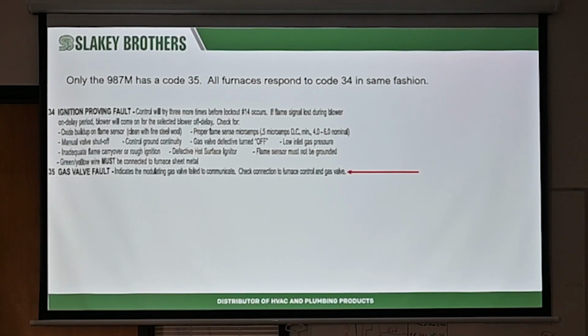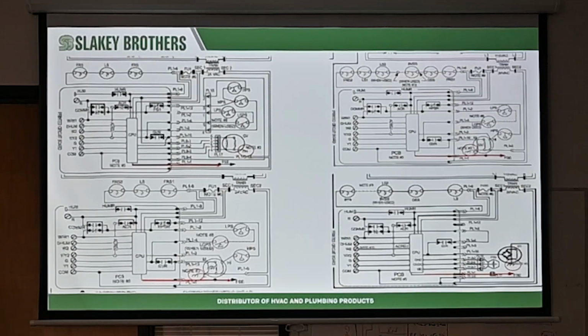Okay? So on 34, again, that's why the very, very first thing it says is oxide built up on the flame sensor. They talk about steel wool, whatever. Man, I've grabbed my brazing kit, taken sandpaper off of there, cleaned up the flame sensor, put it back in there for 17 years, and it works fine. It works just fine. So again, if there's no flame there, then you look for voltage. Okay, so here's our flame sensor circuit.